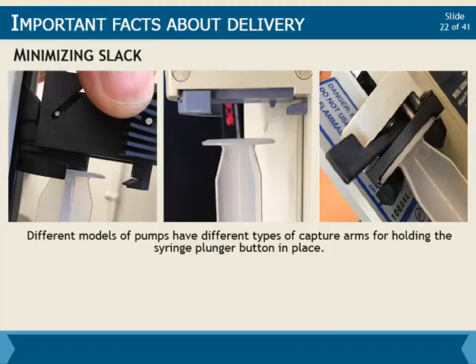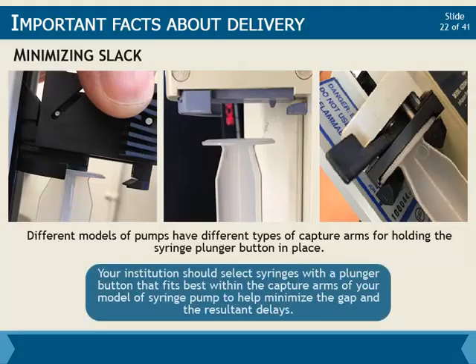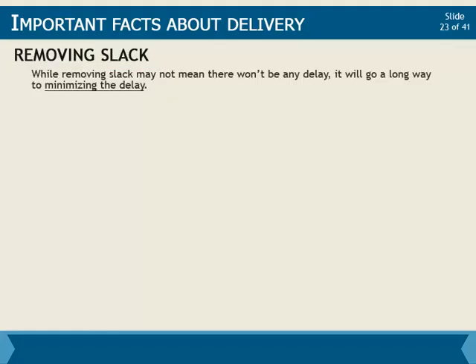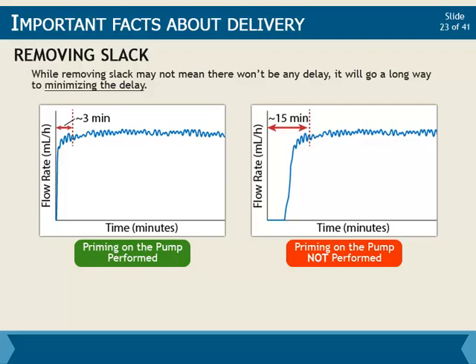These capture arms may not be designed to tightly hold all the different makes and sizes of syringes perfectly in place. Your institution should select syringes with a plunger button that fits best within the capture arms of your model of syringe pump to help minimize the gap and the resultant delays. While removing slack may not mean there won't be any delay, it will go a long way to minimizing the delay. For example, priming on the pump may reduce the delay to a matter of a couple of minutes rather than upwards of 10 minutes.